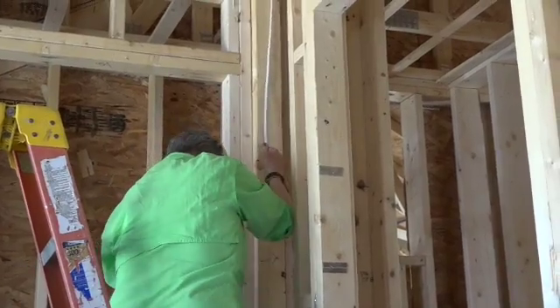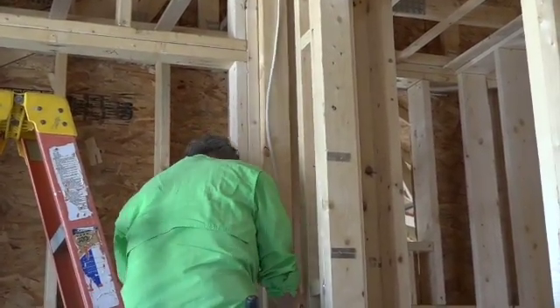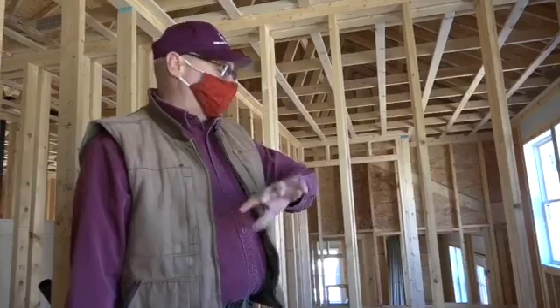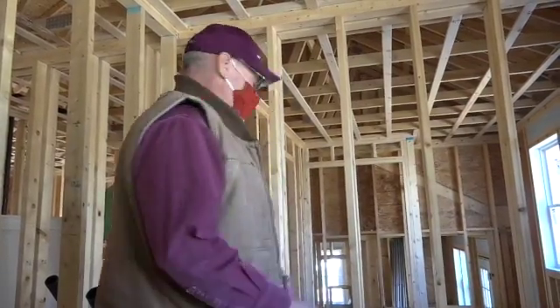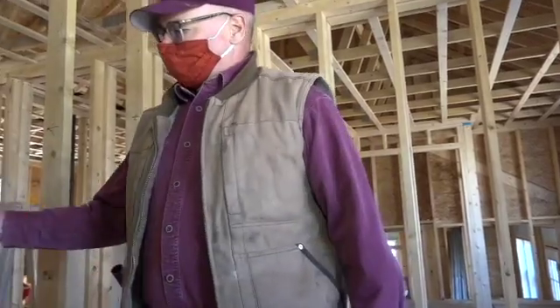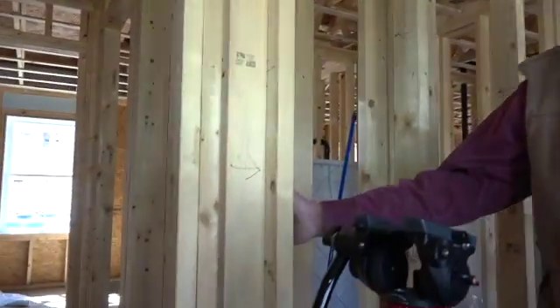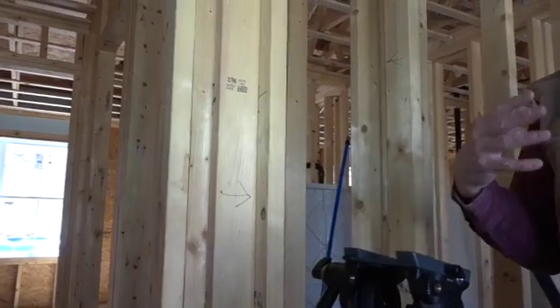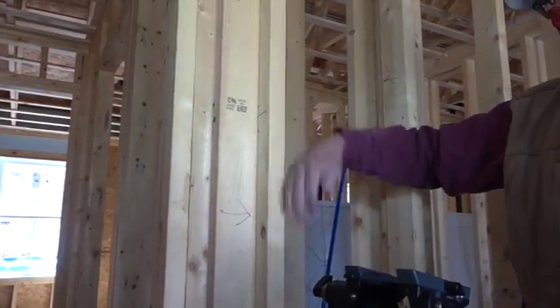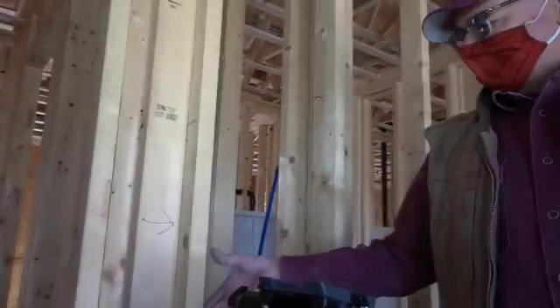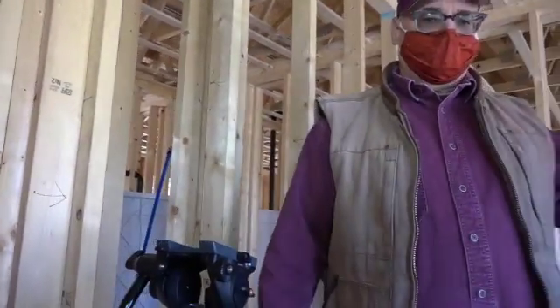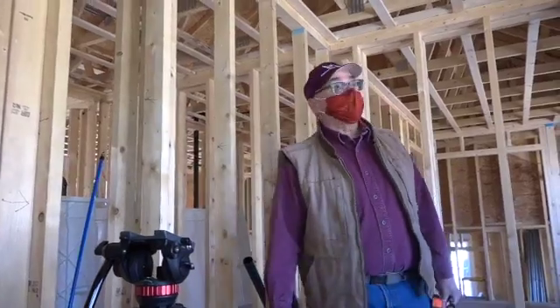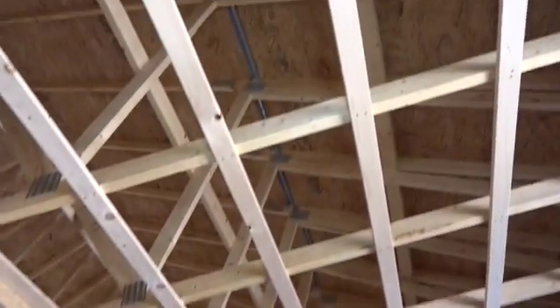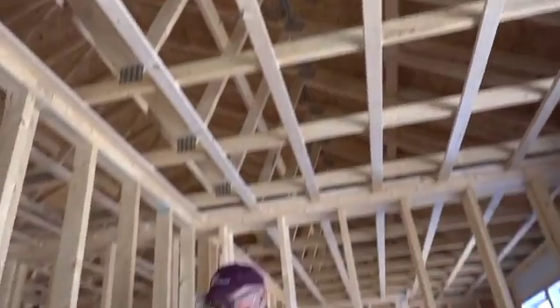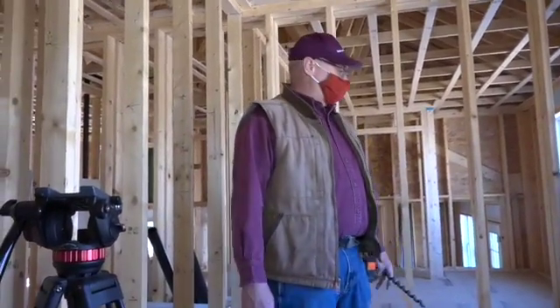And then there's a wire that will jump between the boxes. For this bedroom, it's going to be all one circuit. We'll be mounting a switch box here for the light when coming into the room. The door will be swinging away, going that way, and there'll be a switch box here to turn the lights on. There'll be a ceiling fixture for the lighting in the room. And pretty much, that is the typical electrical in a bedroom.